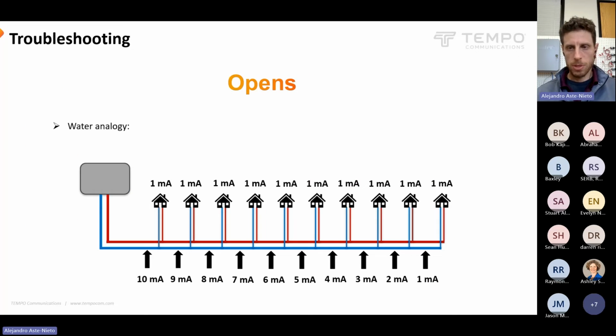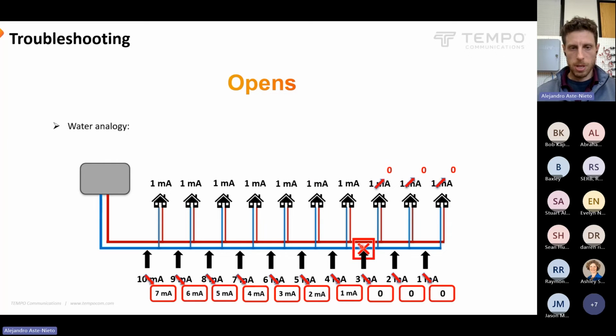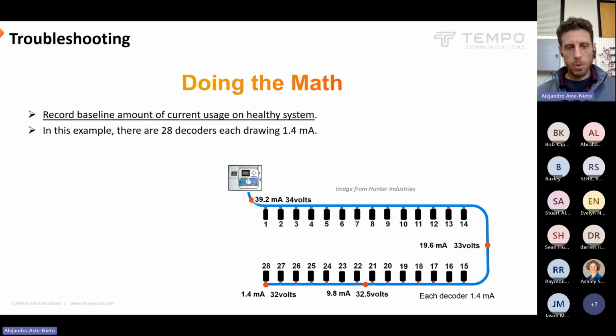What that might look like in this house analogy: if somebody shut off a valve here and these 3 houses don't get water service all of a sudden, it's affecting your amount of water usage upstream as well, and then nothing is happening down here in the water main. So in a more real world situation, when we're doing the math and comparing these numbers, it's best to look at your system when it's healthy and record the baseline usage. We can do the math ourselves and say, we have 28 decoders and they should each be using 1.4 milliamps, but it's better just to take a baseline reading of a healthy system and know when that changes.